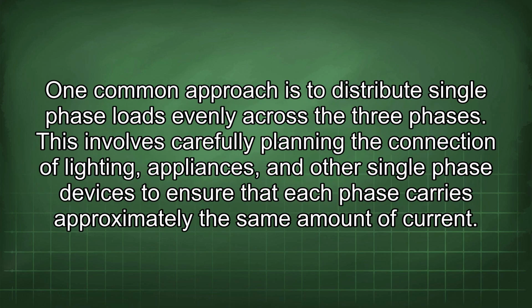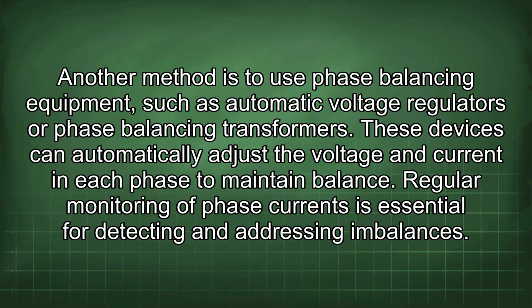One common approach is to distribute single-phase loads evenly across the three phases. This involves carefully planning the connection of lighting, appliances, and other single-phase devices to ensure that each phase carries approximately the same amount of current. Another method is to use phase balancing equipment, such as automatic voltage regulators or phase balancing transformers. These devices can automatically adjust the voltage and current in each phase to maintain balance.